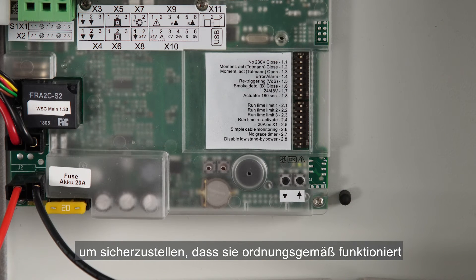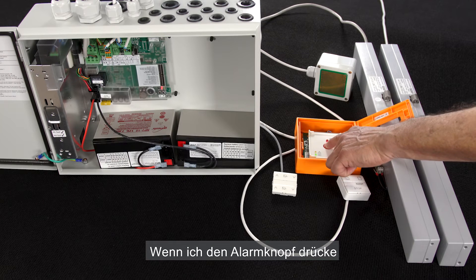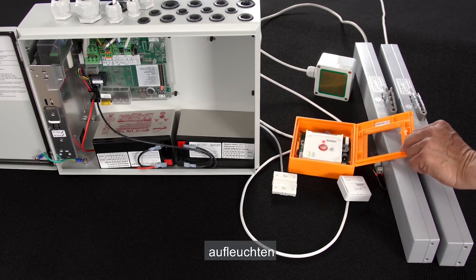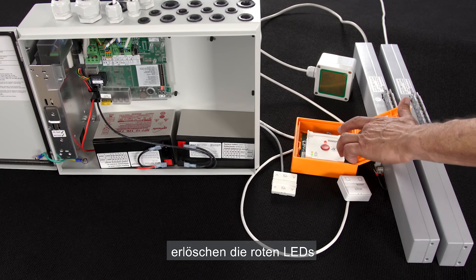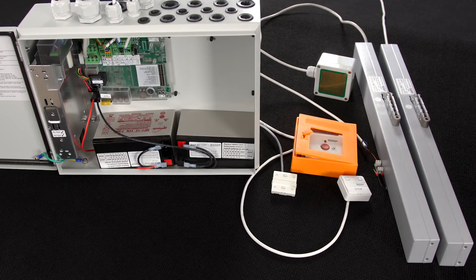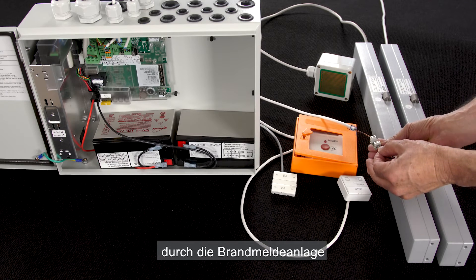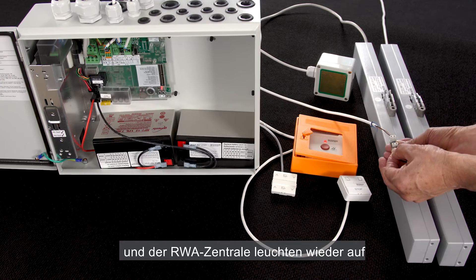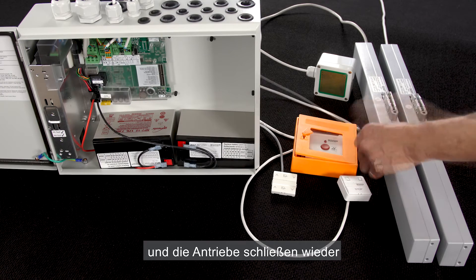Let's test it to see if it works. We can start by testing the break glass unit. If I press the alarm button, we see that the red LED on the break glass unit and the red LED on the panel are switched on, and the two actuators are opening. We reset and see that the red LEDs are switched off and that the two actuators are closing. Now I will simulate the activation of the alarm from the fire alarm system by closing this contact. Again, the two red LEDs on the break glass unit and the control panel are on, and the actuators are opening. When I open the contact, the red LEDs turn off and the actuators are closing.